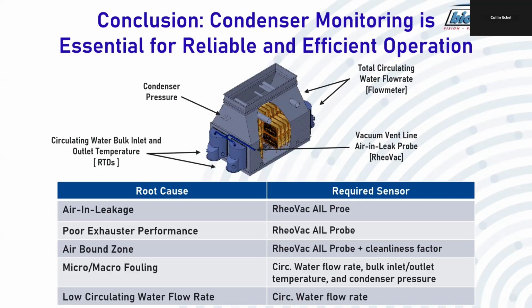Condenser monitoring is essential for reliable and efficient plant operation. With only the few sensors discussed here, you can quickly distinguish the root cause of any increased back pressure as the issue arises, and make effective decisions regarding maintenance and repair.